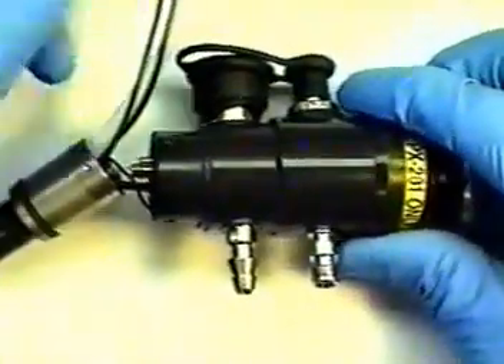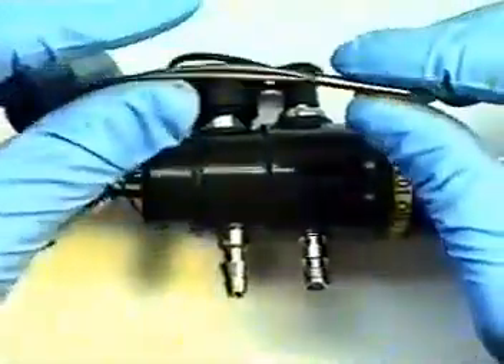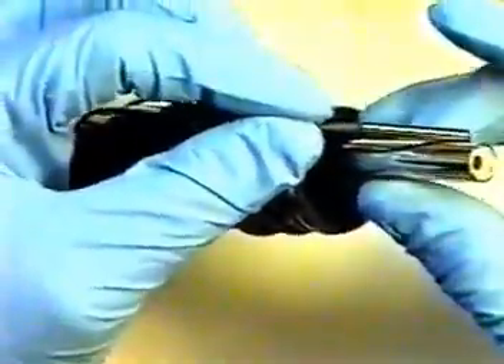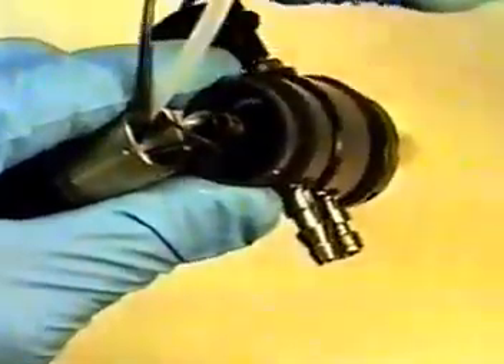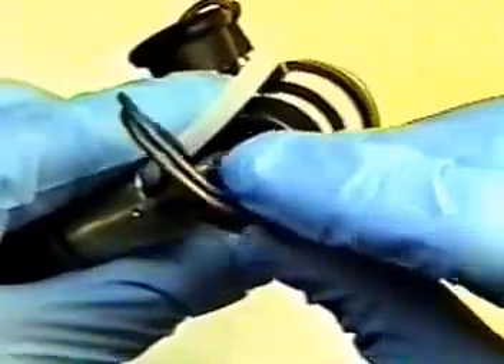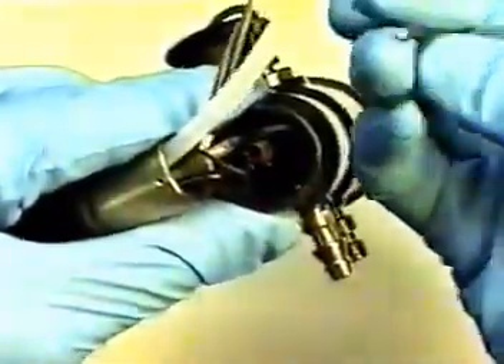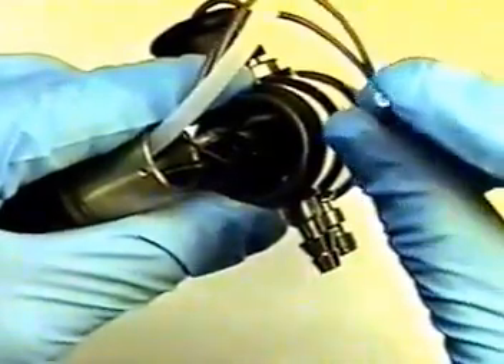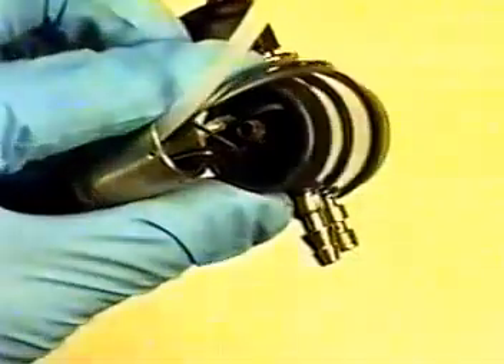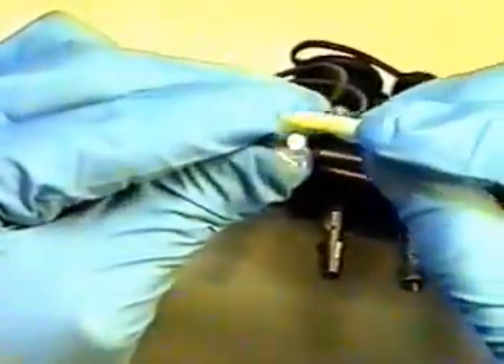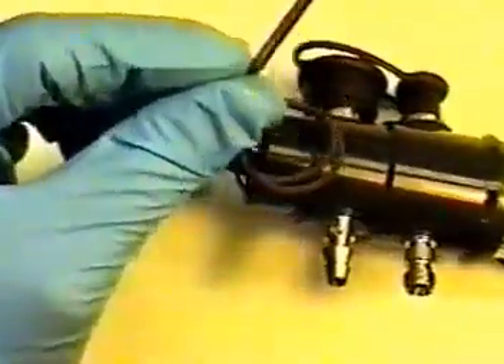We will now work on the connector end. We will pass through the remainder of our illumination light guide bundle through the connector till it meets the end of the light guide probe. In order to do this, we must carefully pass down the light guide probe, being sure that the tip of the probe is clean and free from any debris. You could use some tissue and alcohol to clean off the probe tip if necessary. Any debris on this probe will cause light to not pass through the light guide illumination bundle correctly.